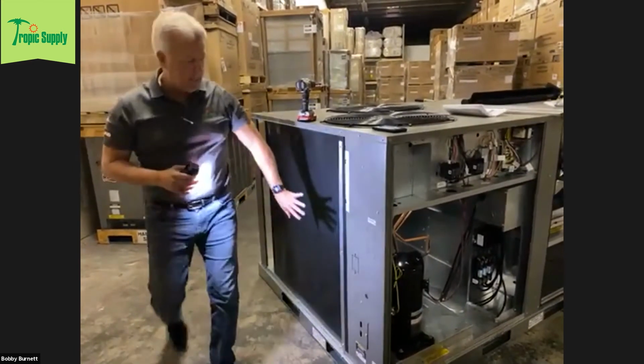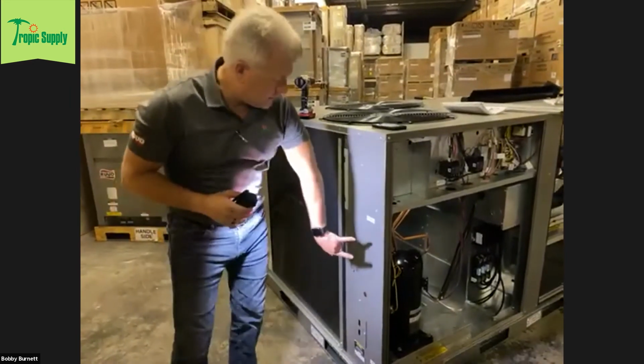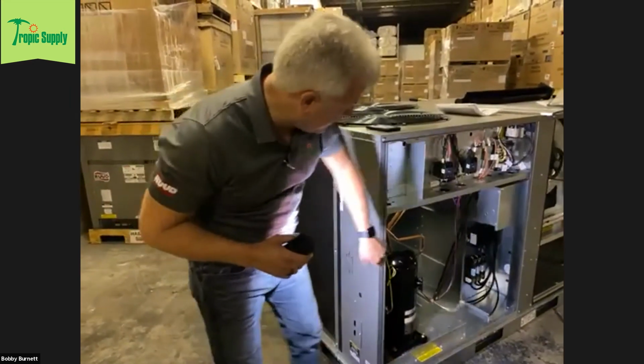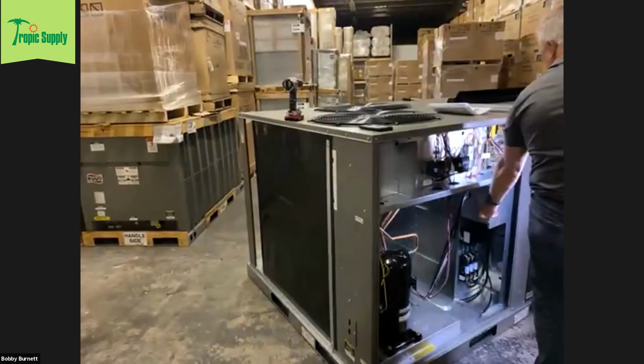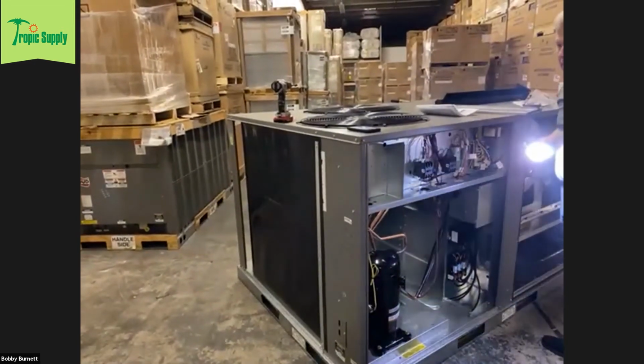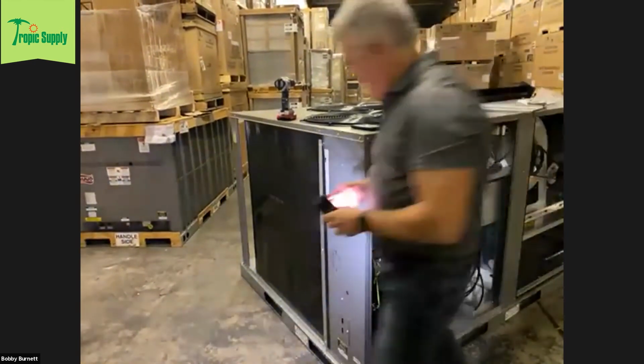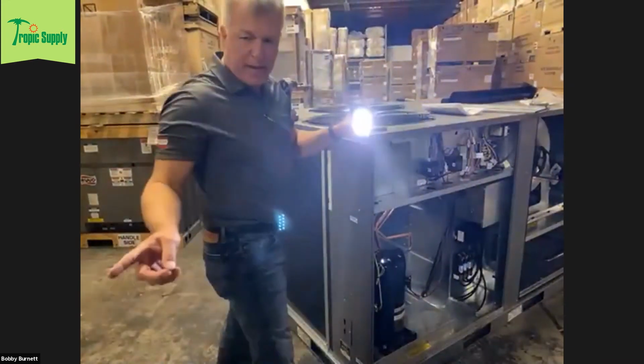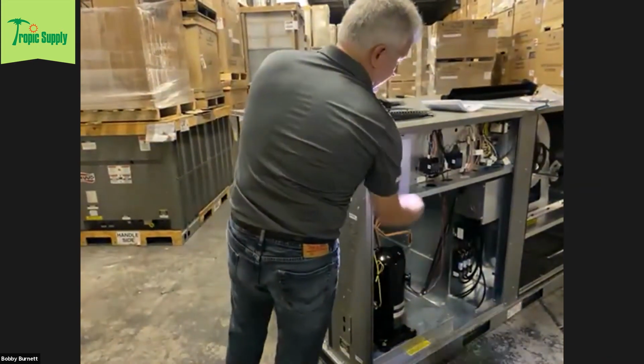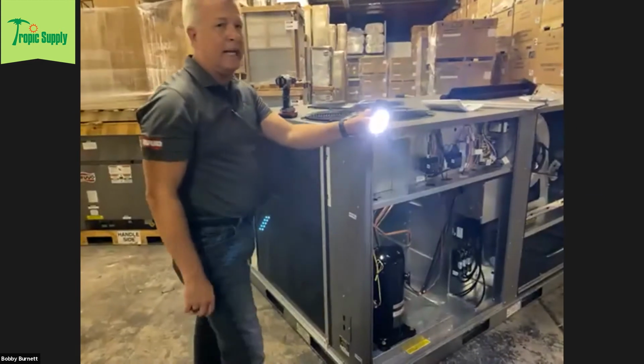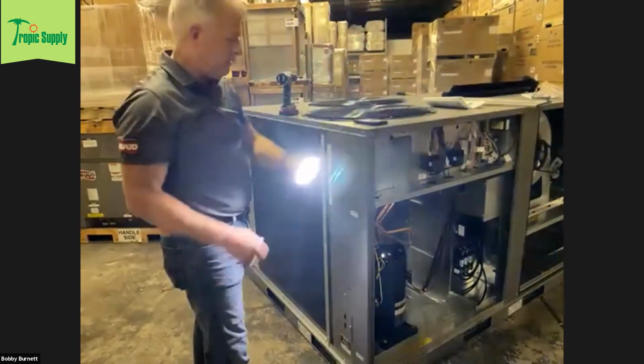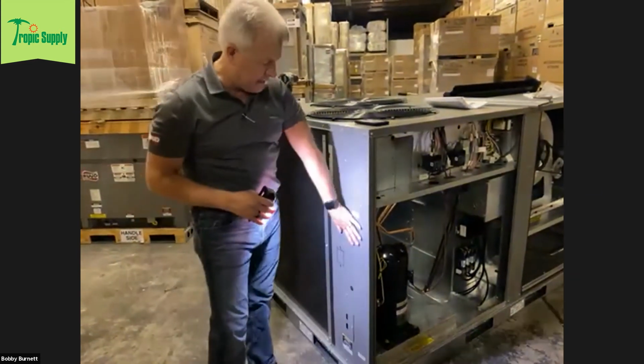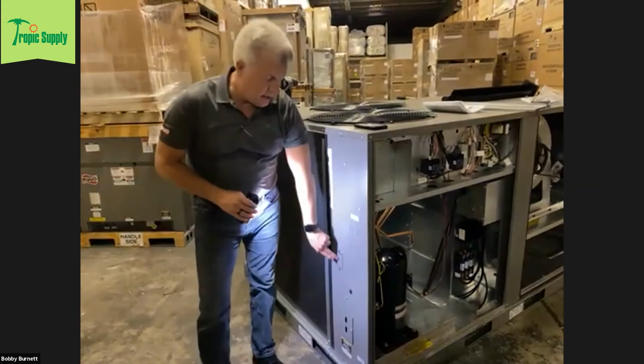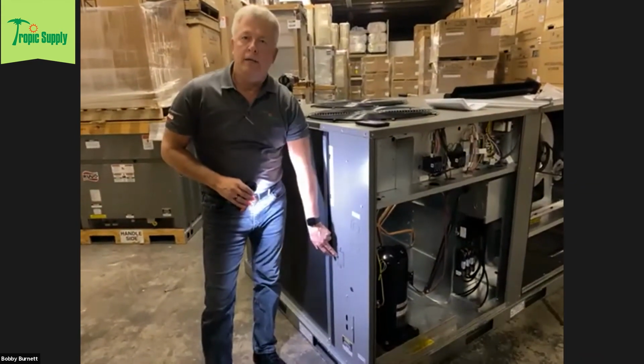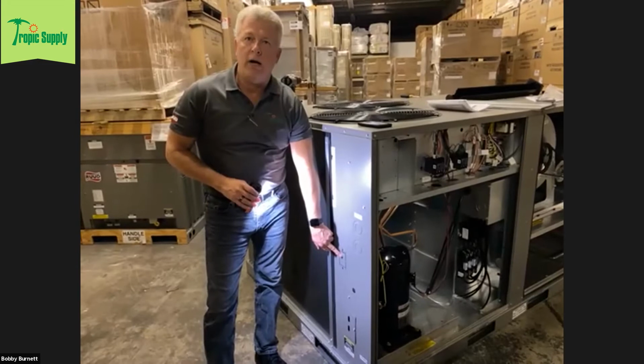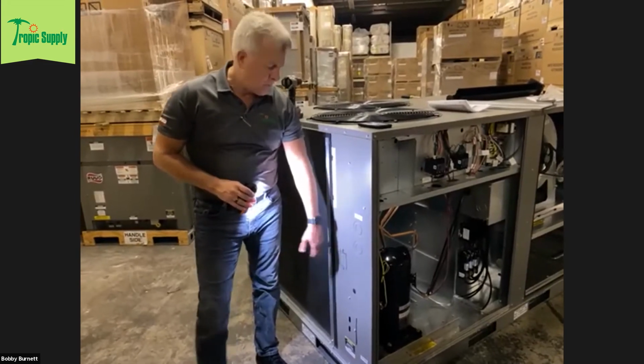You have your line voltage that comes in here, runs across here, and goes into your single point wiring kit. On the actual panel there's a cutout for an electrical disconnect if you wanted to mount one there, a lot of guys mount them over here. This is a knockout for a convenience outlet, either wired or non-wired, that's up to you.